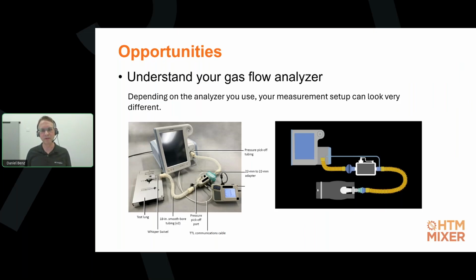So it's important for you to make sure you know how your gas flow analyzer measures relevant parameters, and to check the user manual for setup-specific information. It is really crucial to understand, for example, what is being measured in the main flow channel of your analyzer, and maybe even more important, what is not. Sometimes you have to tee in some different things. So be aware that the wrong setup can lead to significant measurement errors. For example, if you don't tee in oxygen measurement, depending on what you measure, your flow rates can be quite off.